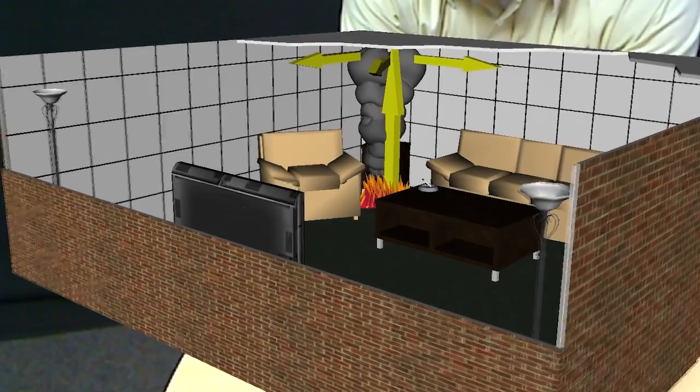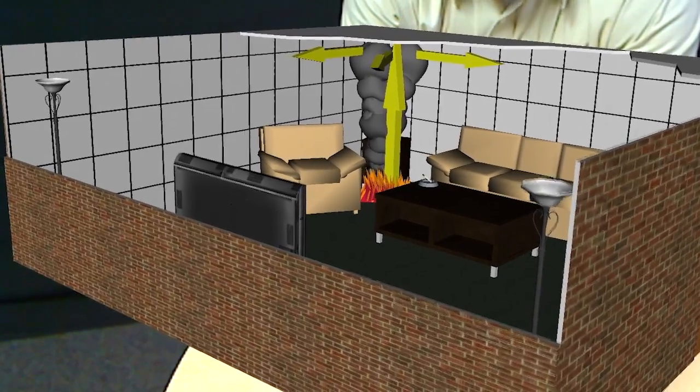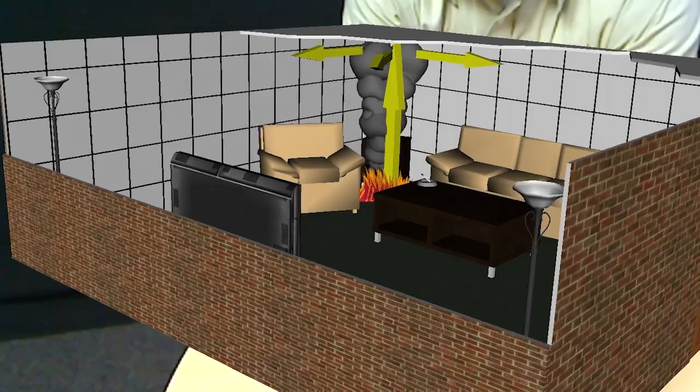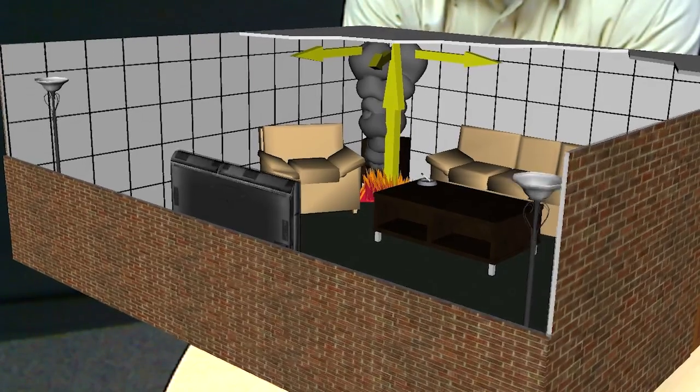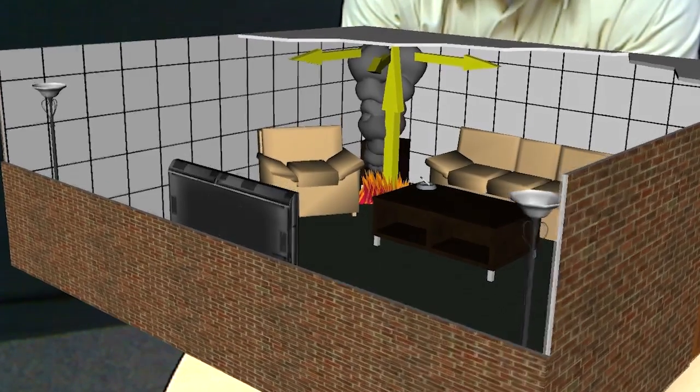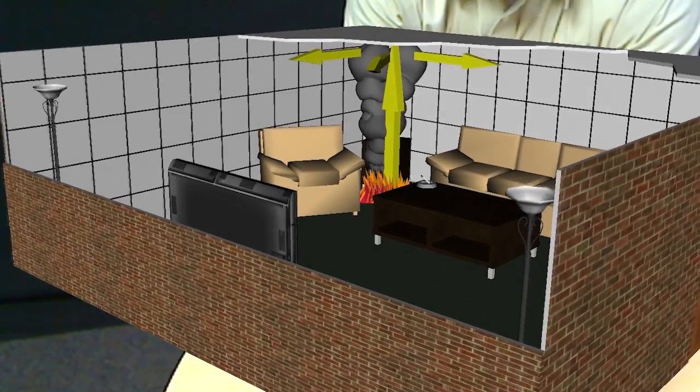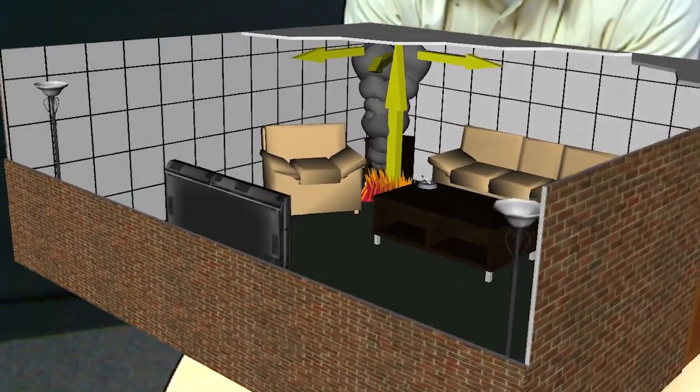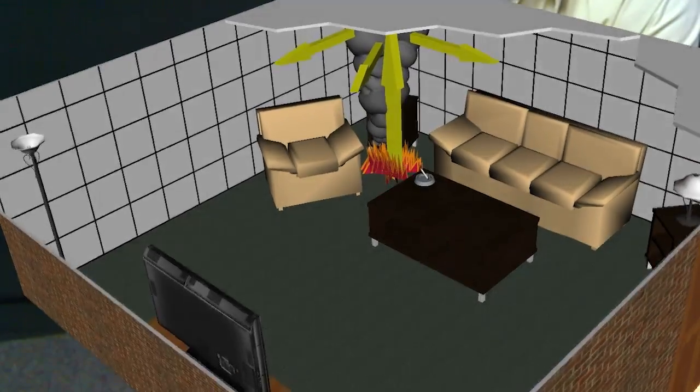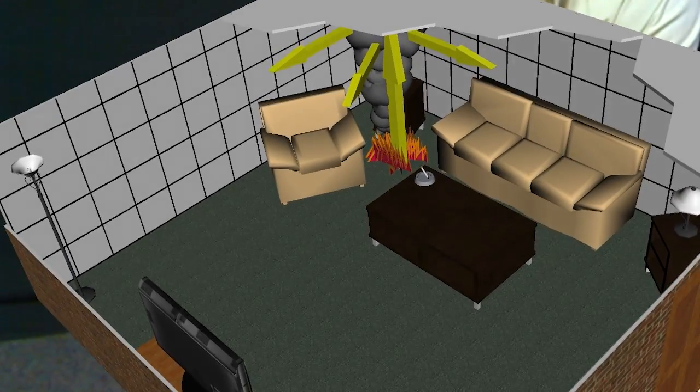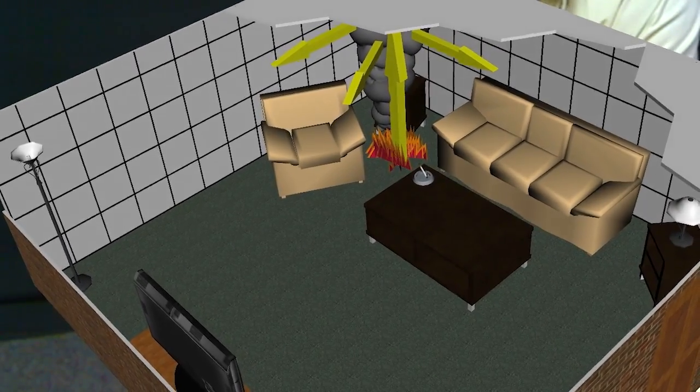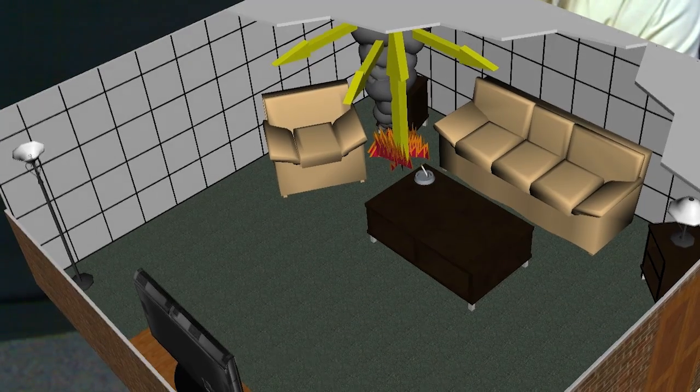And as that smoke rises, it would just rise and eventually stratify out as it cools down. But since we have this in a structure, we have a ceiling. Well, that ceiling forces that flow to go underneath the ceiling. So we get these other yellow arrows that represent what's called a ceiling jet. These ceiling jets are just the redirection of the flow, that thermal plume underneath the ceiling.